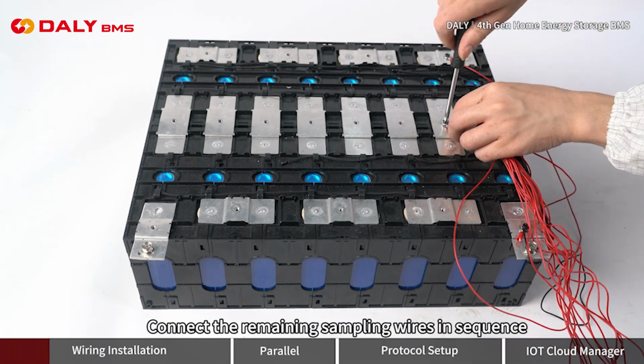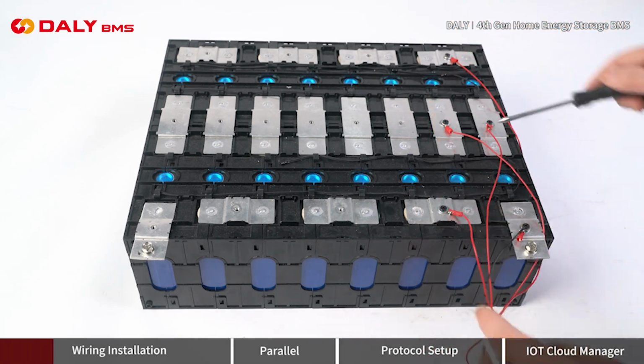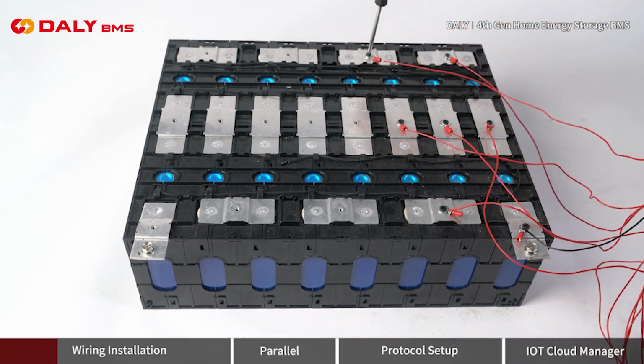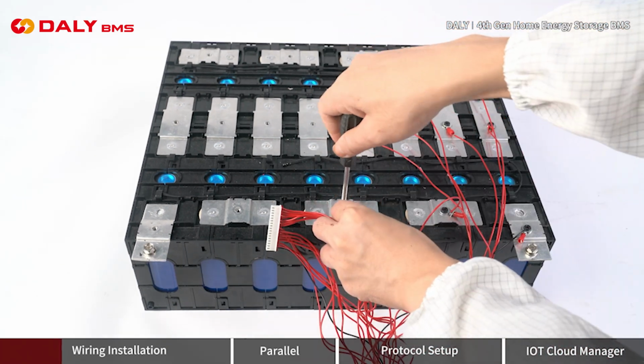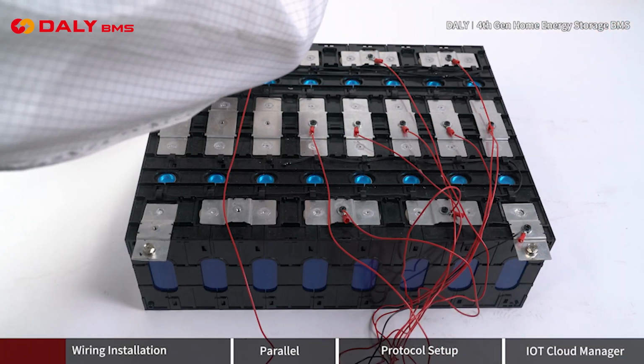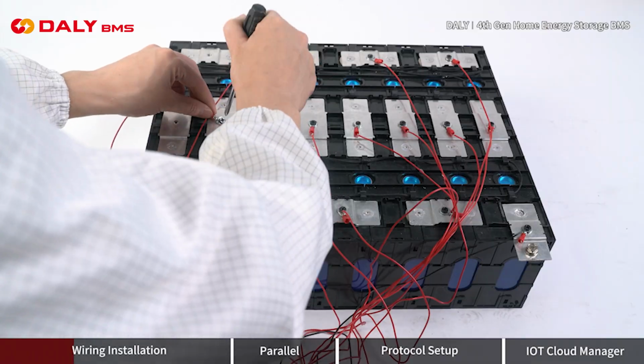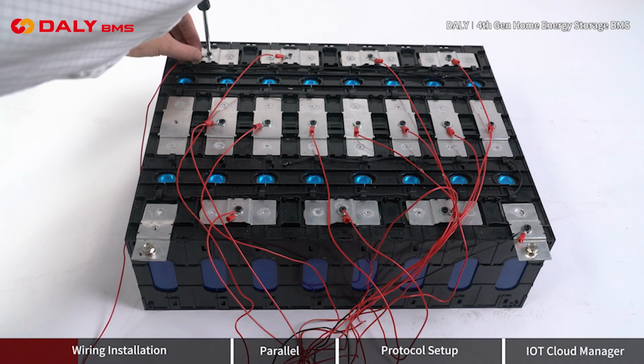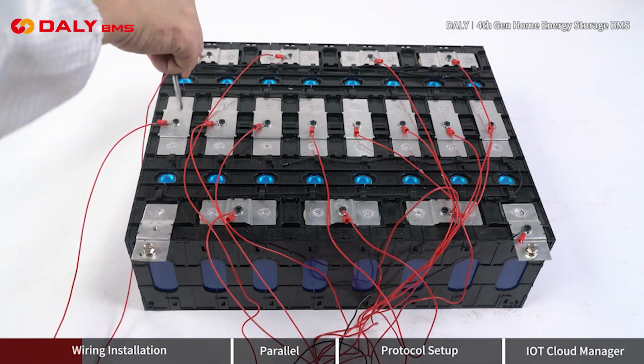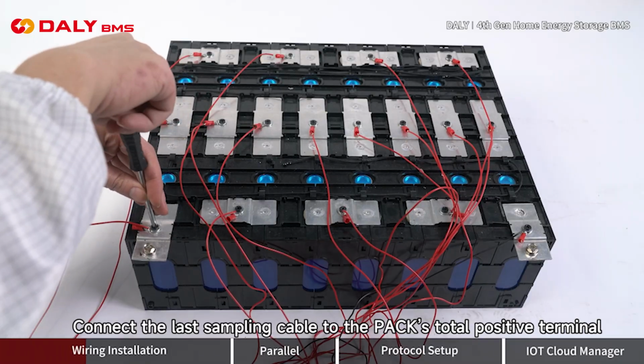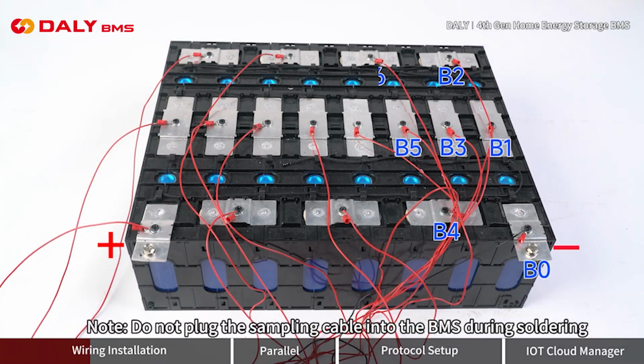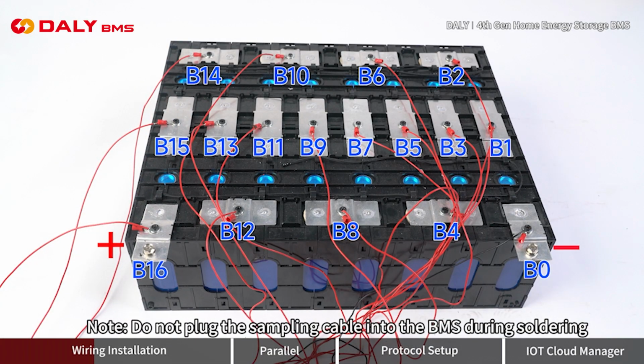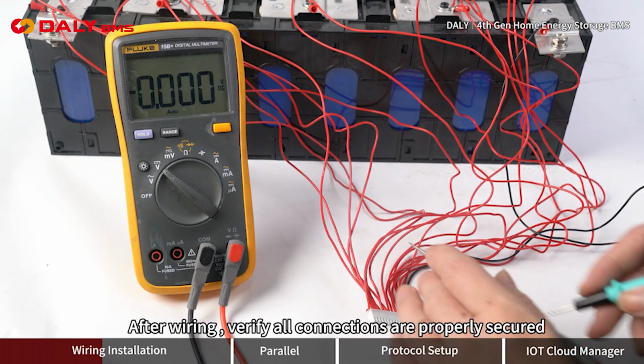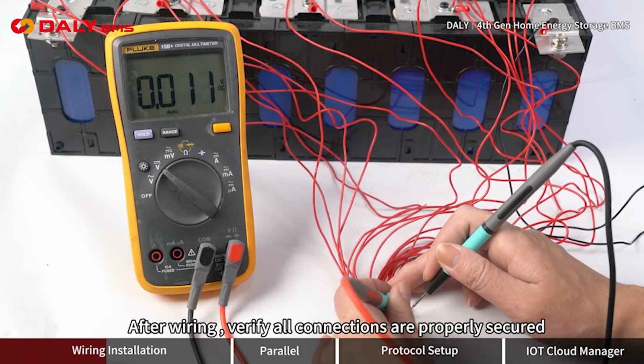Connect the remaining sampling wires in sequence. Connect the last sampling cable to the pack's total positive terminal. Note, do not plug the sampling cable into the BMS during soldering. After wiring, verify all connections are properly secured.